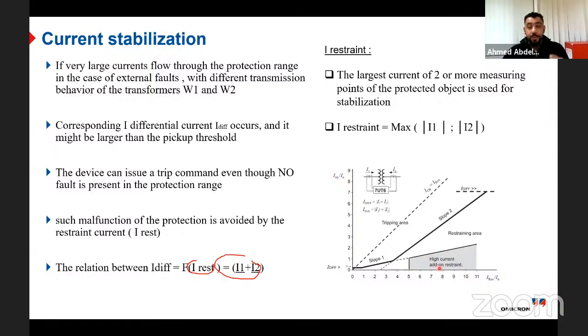It means normally, if I have a fault very close to my current transformer, and it is an external fault, what will happen? The differential current will be 0, and the restraint current will start increasing faster than the differential current, and the differential current will stay at 0. But once one of the CTs is saturated, the differential current will start to increase. So which current starts to increase earlier than the other?